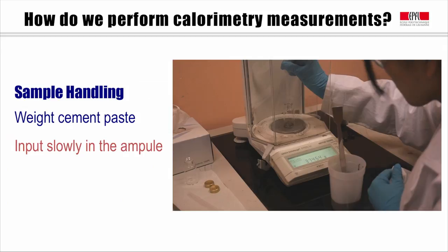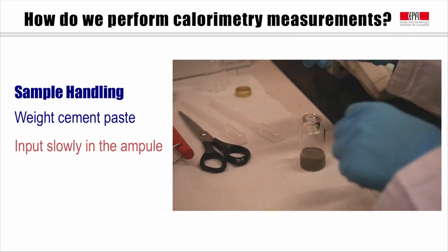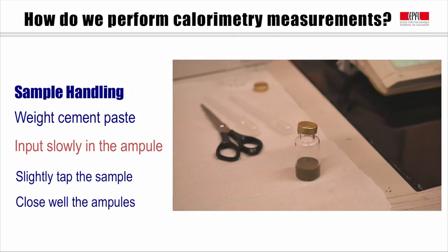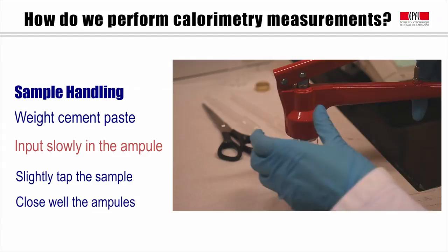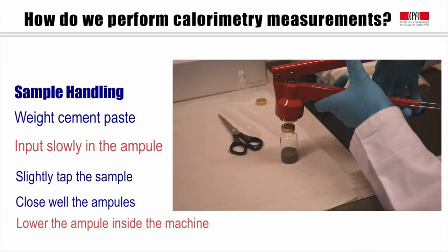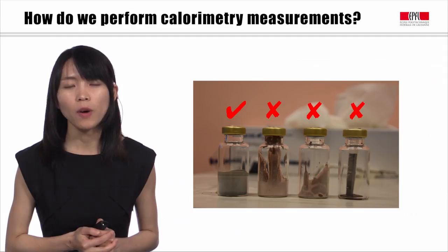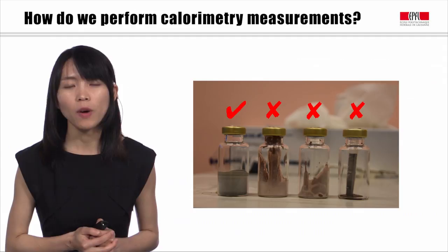After we finish weighing, we slightly tap the sample and then seal the sample with a lid by using a cap clamping tool. Then we can lower the ampoule into the sample side of the channel with the same way as we did for the reference water. Here we have some good and bad examples for the sample preparation. Since the sensor is on the bottom of the ampoule, it is better to put the sample to the bottom to make sure that the heat generated is completely collected by the sensor.